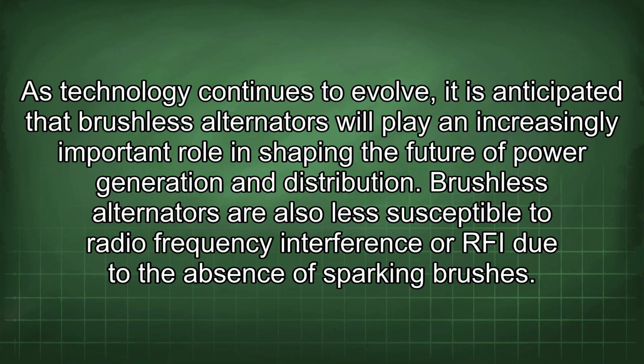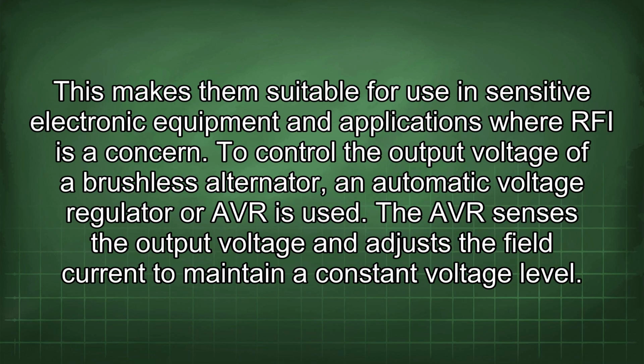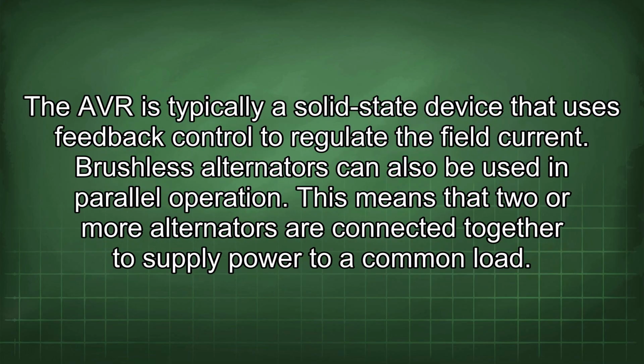Brushless alternators are also less susceptible to radio frequency interference, or RFI, due to the absence of sparking brushes. This makes them suitable for use in sensitive electronic equipment and applications where RFI is a concern. To control the output voltage of a brushless alternator, an automatic voltage regulator, or AVR, is used. The AVR senses the output voltage and adjusts the field current to maintain a constant voltage level. The AVR is typically a solid-state device that uses feedback control to regulate the field current.